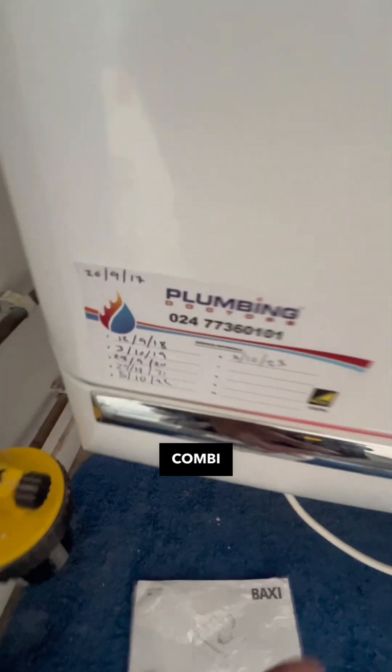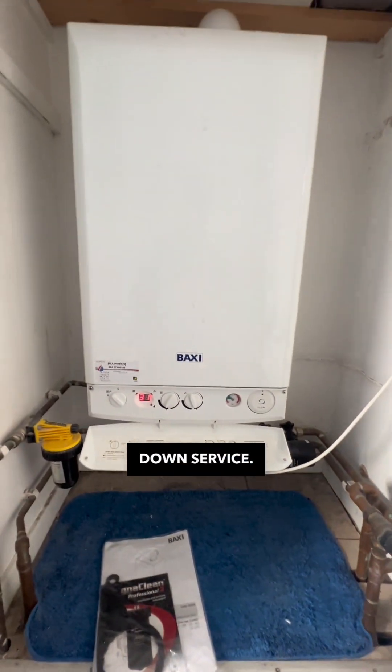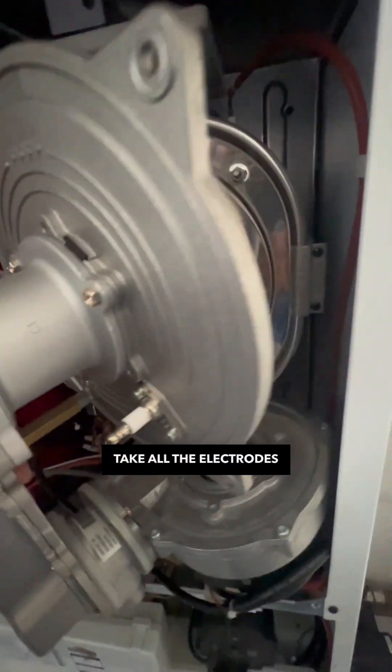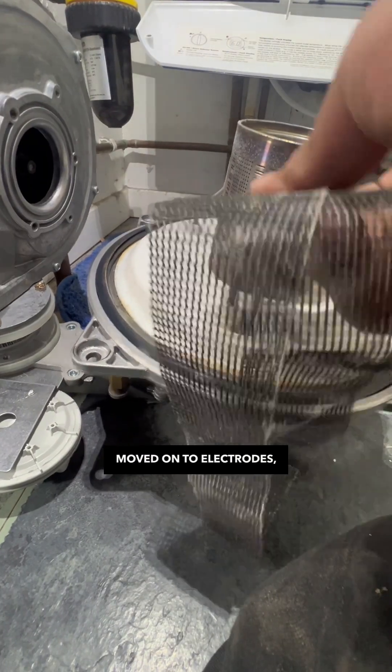Welcome back to your Duo-tec Combi seventh year service — this is going to be a full stripped-down service. Switch the boiler off, turn the gas off, remove the burner and take all the electrodes off. I gave the burner a clean with a soft brush initially, then moved on to the electrodes.